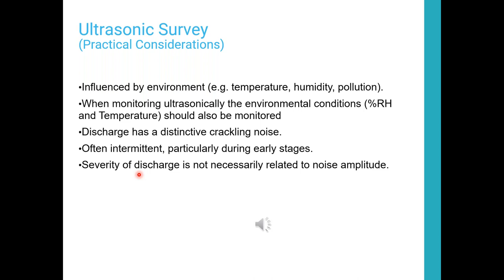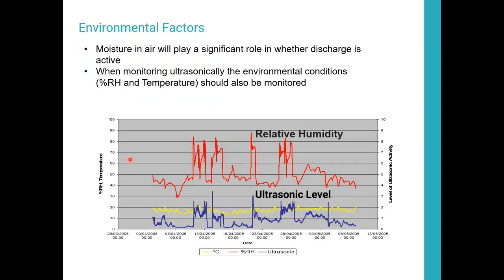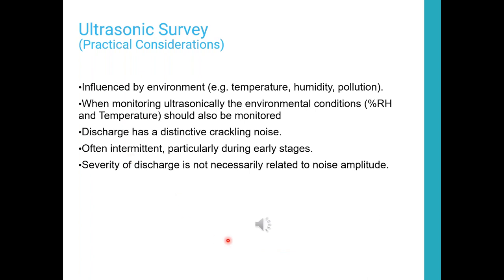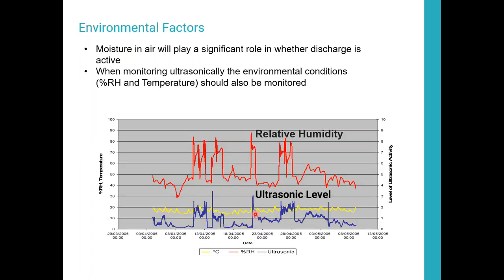Now, you're going to hear background noise, white noise, hissing. You may hear a bearing, a screeching noise. There are a lot of sounds you may hear on your ultrasonic microphones, but when you do find the partial discharge, it's very distinctive. And I've got an audio clip here. I'm not sure if it's going to play. I'm going to try it. Nope, didn't play. My apologies. A lot of times with these webinars, the audio doesn't come through. So I do have to apologize for that. But it's a popping, spitting.